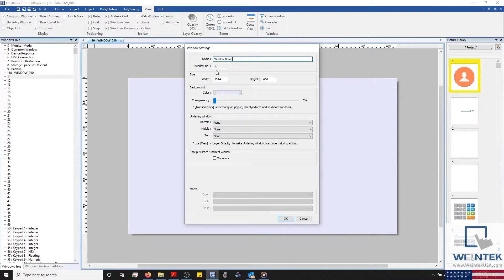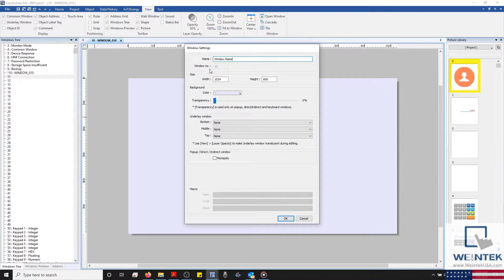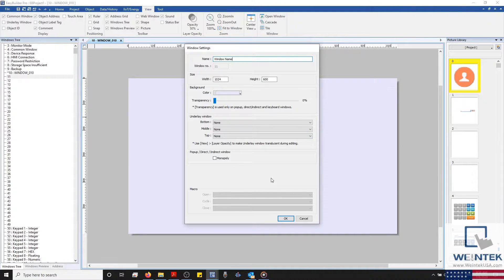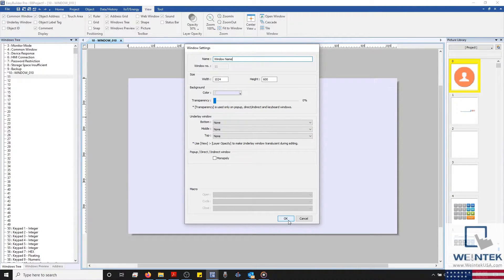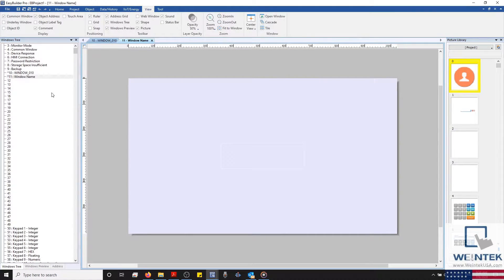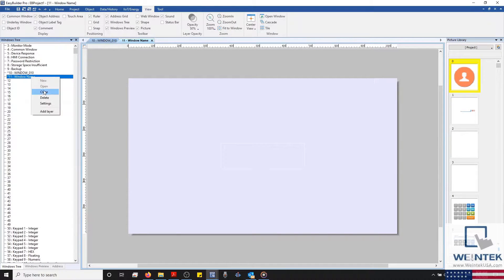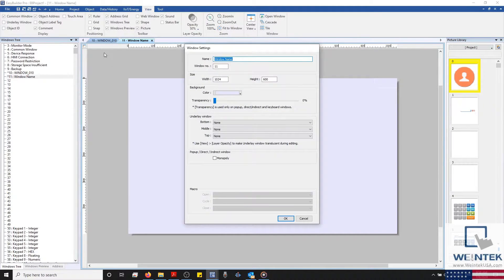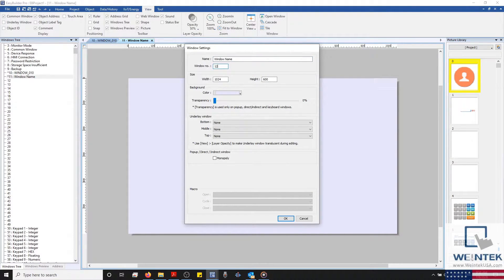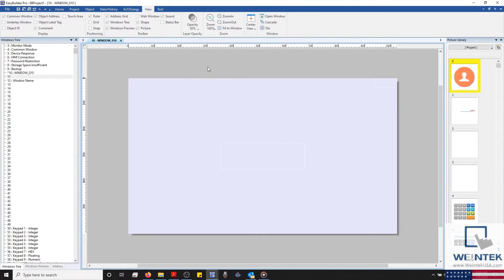Just below our window's name, we'll find the window number associated with your new or existing window. The window number is also used in several objects within EasyBuilder Pro, such as our direct window or PLC control object. And although the window number is already established when creating a new window, the window number of an existing window can be changed to a different number as long as you have a separate window open while doing so.